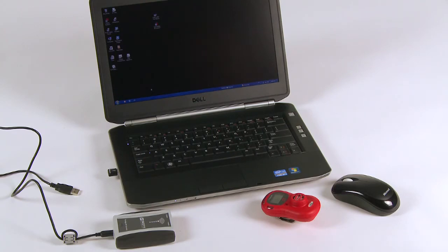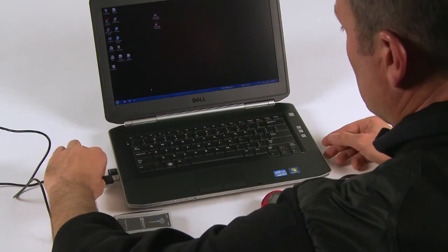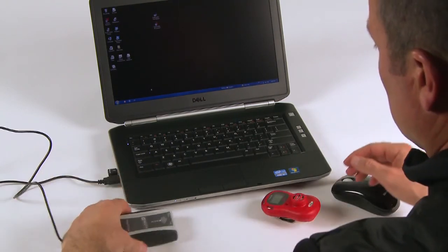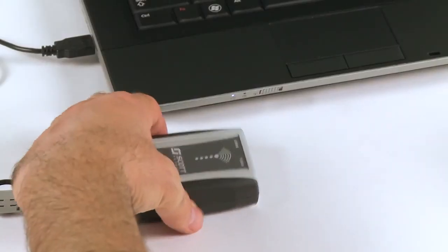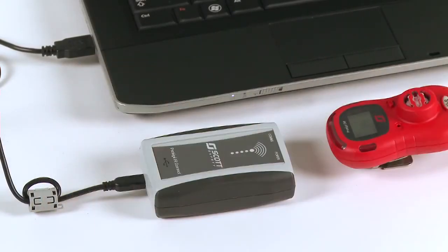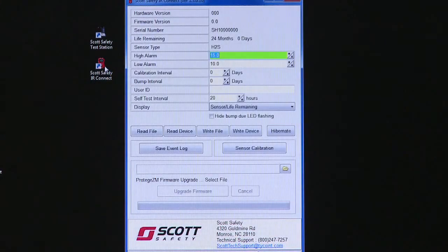To program an individual monitor using the IR Connect, connect the IR Connect USB cable to the USB connector on your computer. Place the monitor about 1 to 2 inches in front of the IR Connect window. Start the Scott Safety IR Connect application on your computer. The software will display a number of settings that can be customized on your computer. Settings for high and low alarm settings, bump and calibration intervals, self-test interval, user ID for the monitor, and display settings can be changed. This screen includes an option to allow you to change the main display of the monitor to show the time remaining, gas concentration level, or both depending upon your preference.